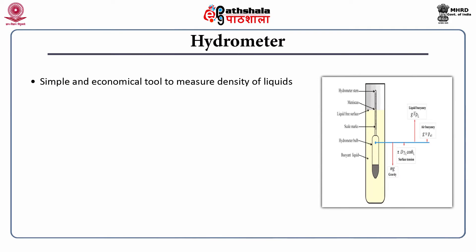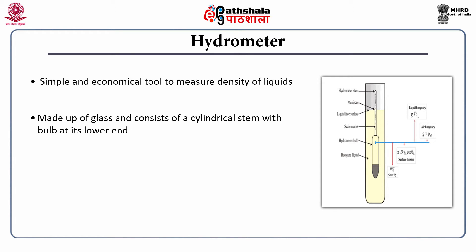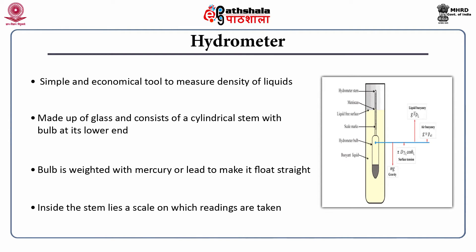A hydrometer is a simple and economic tool to measure density of liquids. It is generally made up of glass and consists of a cylindrical stem with a bulb at its lower end. The lower half has a bulb and the upper half has a stem which is graduated. This bulb is weighed with mercury or lead — generally lead — to make it float straight. Once you dip the hydrometer into water, it shall float, and the calibration on the stem gives you the reading.